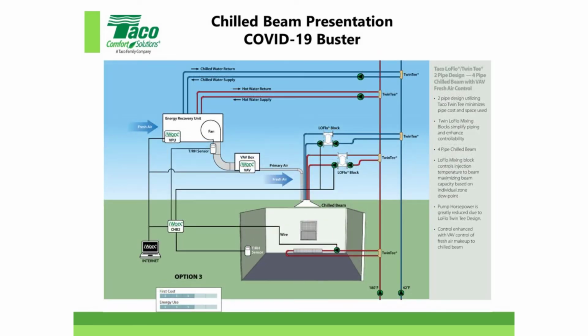Here's another way you can do it as well. This is option 3, where we actually put a VAV box and control the primary airflow into here. So I would recommend that for a big classroom like ours, or a big room like this. For an office or something like that, you probably wouldn't need to control that airflow, but we have seen people do that. You can still see the piping system is the same there as well, so something to consider. I'm going to design a system using our software.